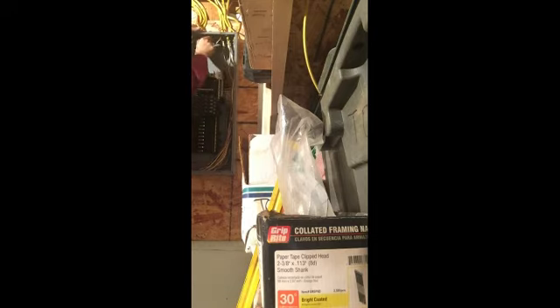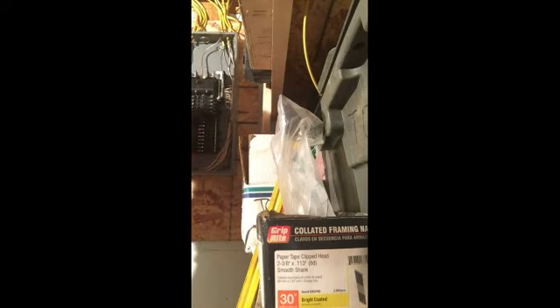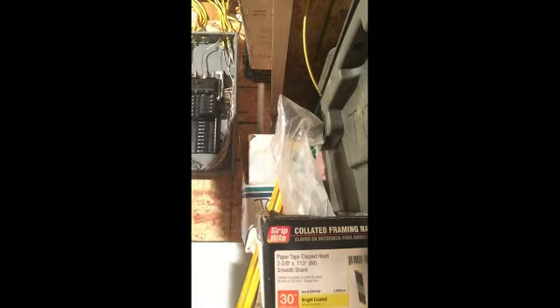Once that bar has 110 volts, it'll be on one side of your circuit panel box for your breakers. You can throw all the breakers one at a time and test the switches and the circuits in the house. I went ahead and did that. And then I turned off the generator and switched it to the other 110 leg, which in a house you have 2-phase electricity, which is you have 2 separate 110 volt legs that come in. So I had to switch the 110 volts from the generator over to the second leg, which is the next column of your circuit breakers.